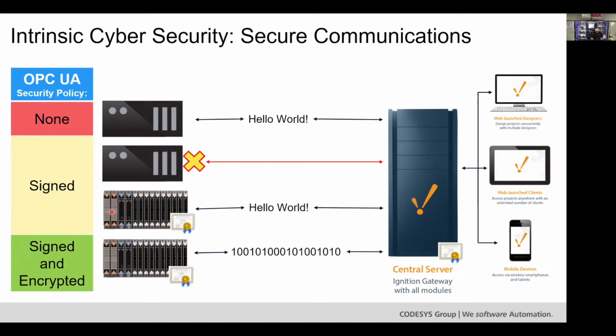The optimal configuration is a security policy of signed and encrypted. This means you have a certificate on both the controller and server side, and the data going back and forth is completely encrypted. Not only can only authenticated devices connect to the server, but that data is also completely unreadable to anyone not authenticated. That's a huge part of implementing security into your system—securing the data from controller to SCADA, knowing who's connecting, and making sure the data is non-readable by any other system.